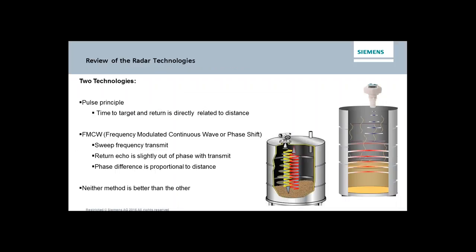There are two base technologies for radar: pulsed radar and FMCW (frequency modulated continuous wave). Whether it's a pulse measuring time of flight or FMCW measuring a phase shift, there isn't an appreciable advantage to one over the other in terms of accuracy or performance. Pulse radar sometimes works a bit better in low-power or loop-powered applications, while FMCW is typically used where you have line voltage — 120 or 240 volts — powering the radar unit.